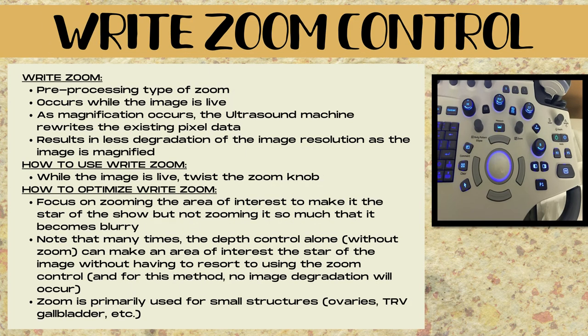The second type of zoom is write zoom, and this is a pre-processing type of zoom. All ultrasound machines will have write zoom, whereas many ultrasound machines may not have post-processing functions and may not have read zoom.